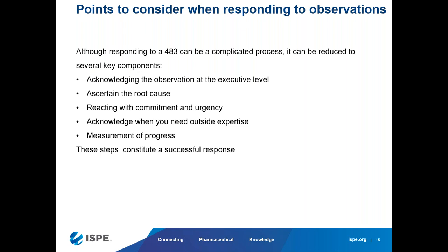Let's say, for example—no, not a good example. Say we didn't do maintenance of our HEPA filters, and we just did a filter integrity test, nothing else, once in 2 years. Well, where is the regulation? There is no specific regulation; it just says maintain your facility. So where do I go next? I go to my standards. So where is the standard? If I look at 14644-3 from 2015, well, it was not accepted by the USA, so for US FDA that doesn't apply.